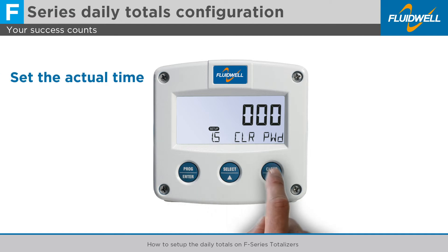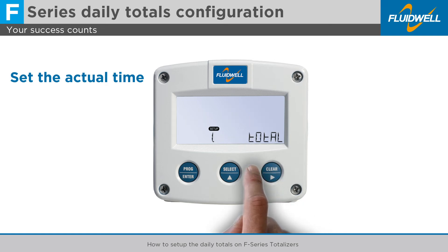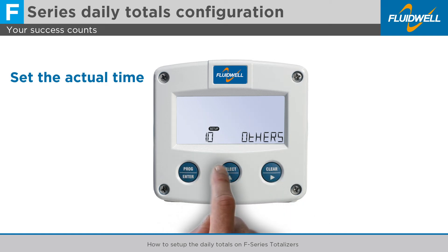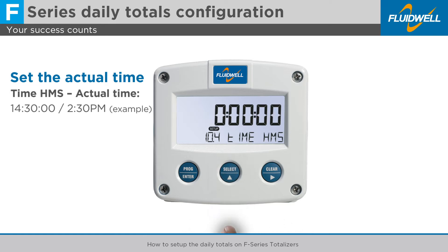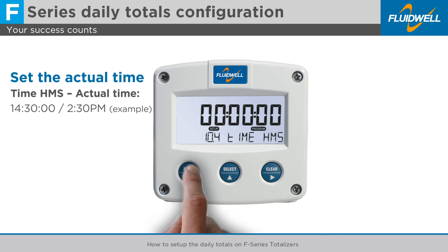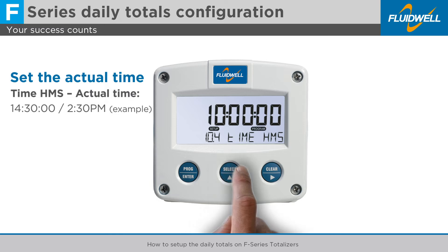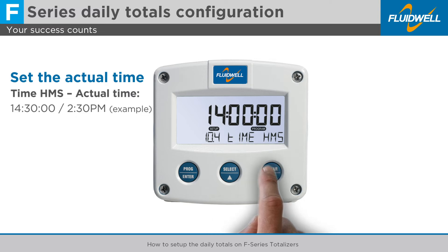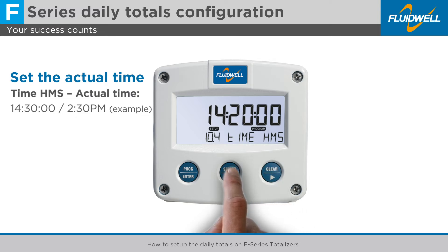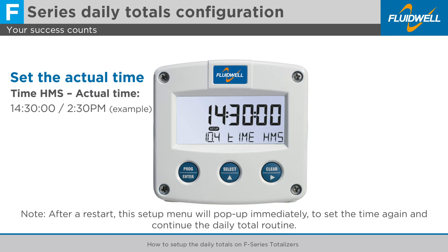Use clear or prog to go to menu 10, others. Press select to go to menu 10.4, time HMS, to set the actual time with a 24-hour clock. Press prog to change the time setting. Use select and clear to set your actual time — for this example, 14:30. Press prog to store this setting. After a restart, this setup menu will pop up immediately to set the time again and continue the daily total routine.